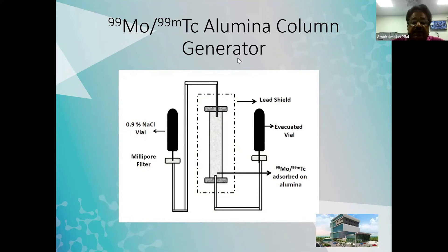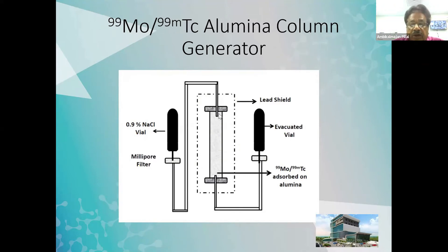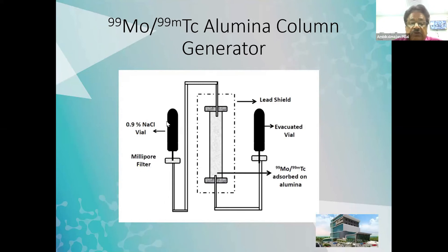What happens in a technetium generator? This is the core component: you have an alumina column. This alumina column is loaded with molybdenum. The molybdenum is absorbed onto the alumina column and will not come out. Then you take a small amount of saline — maybe about 5 ml — and pass it through the column. The pertechnetate will be eluted and you will get pertechnetate ready for your nuclear medicine studies.